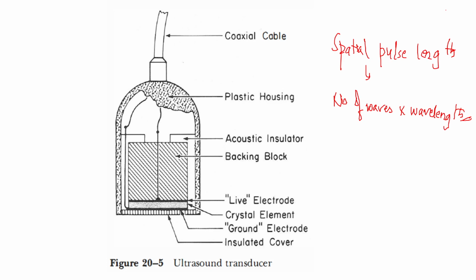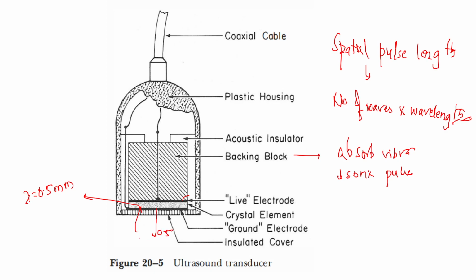Then the next important thing that you have to learn is the backing block. The backing block will absorb some of the vibrations, and it will shorten or decrease the sonic pulse. If the wavelength of the sound at the transducer is around 0.5 millimeters, this will go to the tissue and be received back. When it is received back, the pulse is received after two wavelengths. The number of waves is two and the wavelength is 0.5. So the spatial pulse length here is 2 times 0.5, which is equal to 1 millimeter. So the ultrasonic pulse should be of a single wavelength.